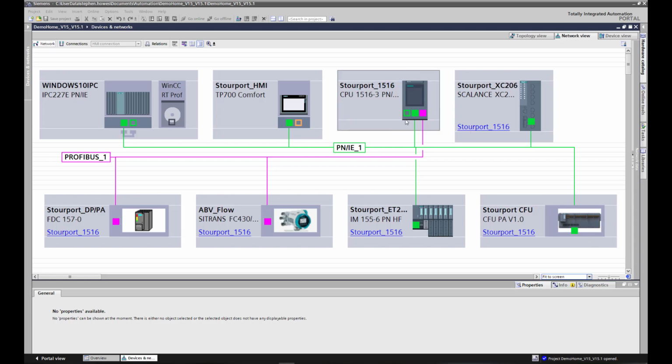And then I have my PLC, and on here there's two Profinet ports, and then there's a third one which is nicknamed the not Profinet. Now this is important because the PDM maintenance station is going to sit on the same network. So you can see here, this is a PC that's got just WinCC Runtime Professional, a low cost industrial PC. But sat on the same network, I haven't got a picture of it because as far as TIA Portal was concerned, it's transparent.